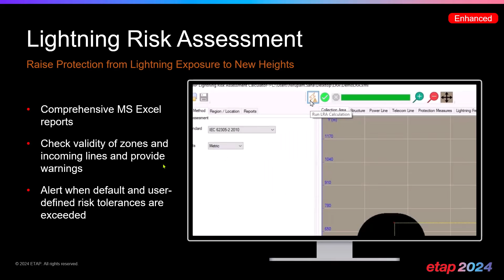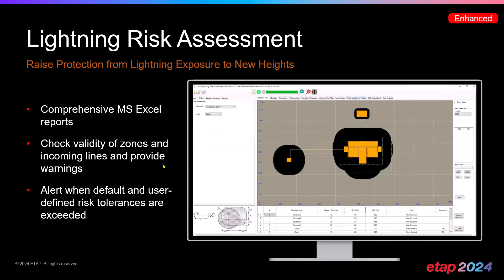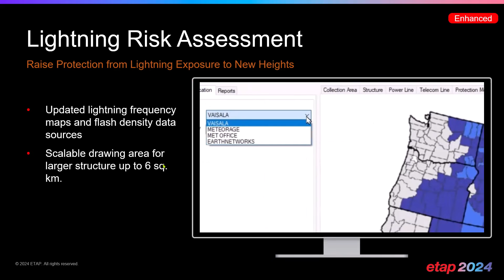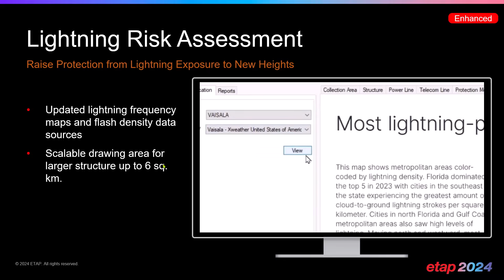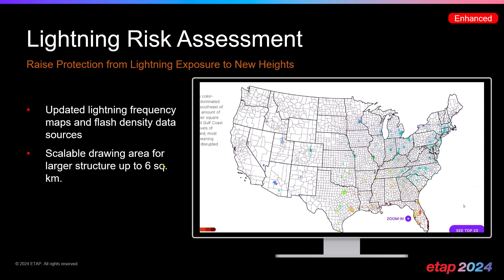And of course, lightning risk assessment requires input from weather data such as lightning frequency, and the lightning frequency maps and the flash density data has also been expanded to include more parts of the United States as well as global regions. And you can also include a drawing area of the lightning protection system evaluation for structures up to 6 square kilometers, allowing us to model very, very large structures and analyze them in multiple zones all at the same time.